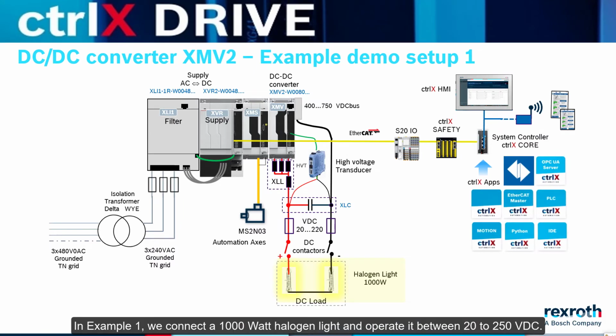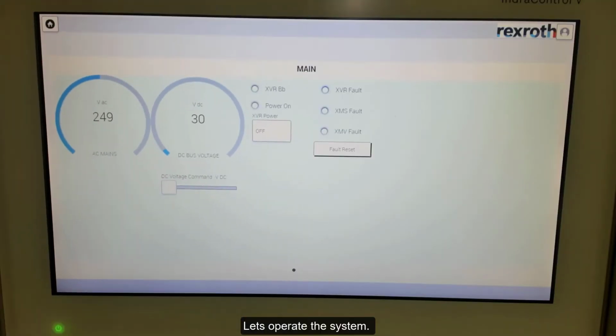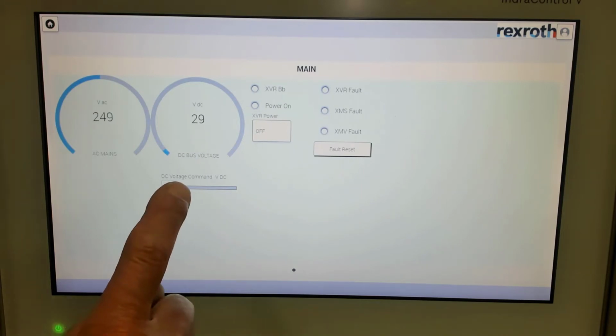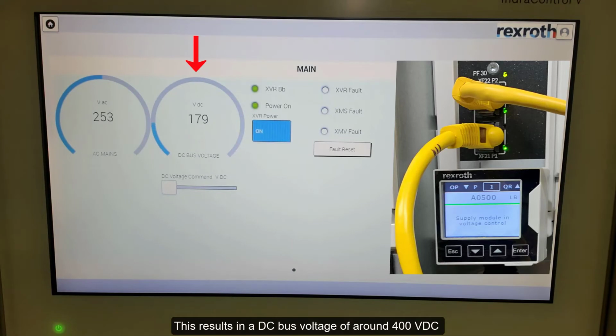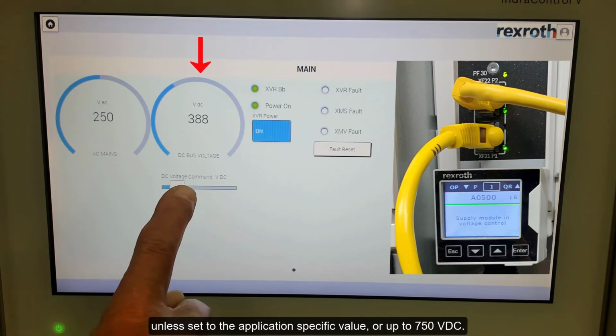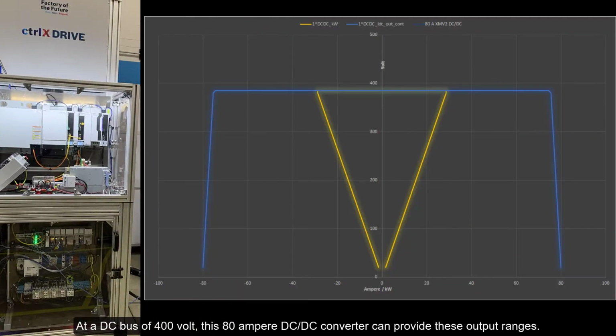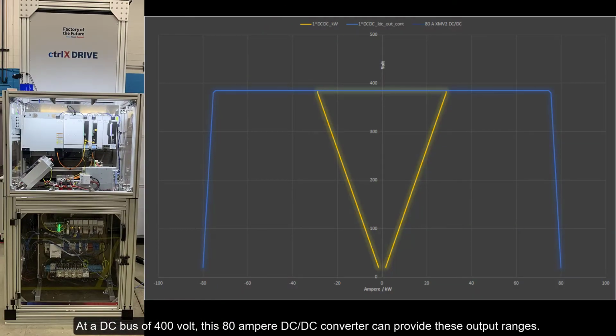In example 1, we connect a 1000 watt halogen light and operate it between 20 to 250 volt DC. Let's operate the system. The line voltage at the supply XVR2 is 250 volt AC. This results in a DC bus voltage of around 400 volt DC, unless set to the application-specific value, up to 750 volt DC. At a DC bus of 400 volt, this 80 ampere DC-DC converter can provide these output ranges.